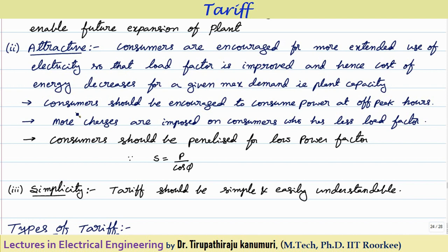Consumers should also be encouraged to consume power at the off-peak hours. For example, during the daytime all the industries will run, during the evening household loads will be there, but in the night time industries and offices are closed, so the load on the station decreases and the overall load factor of your station decreases. To compensate and increase the load factor, we can encourage some consumers to use energy during the off-peak hours. For example, in cities the municipalities' water pumping systems are generally used in the night time because some extra facilities are provided for consuming in the off-peak hours. I am going to take one example of the power bill used in Delhi to explain all these things in detail.